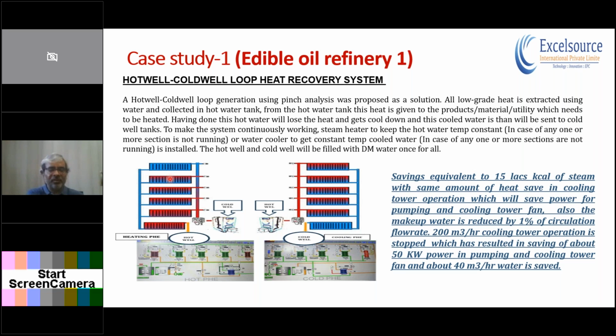and then generated hot water, which comes at an average temperature and goes to a hot well. The temperature of that hot well is about 90 degrees Celsius. From this 90 degrees Celsius, we are taking this heat to all the heating requirements in the plant, not in one particular section, but across the plant. We have distributed this hot water and given the heat to the cold materials, or cold water, to be heated, and then it comes back to the same low temperature, which is required to circulate again to extract the heat from the hot circuit.